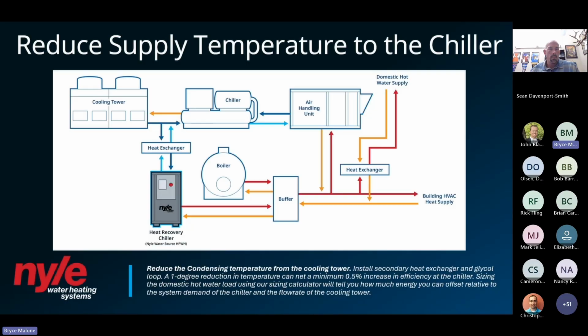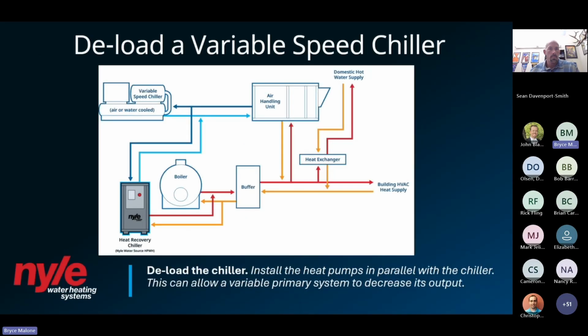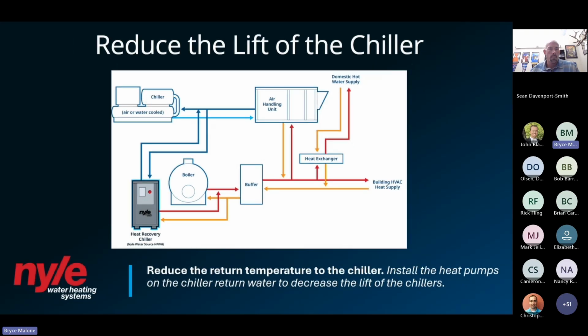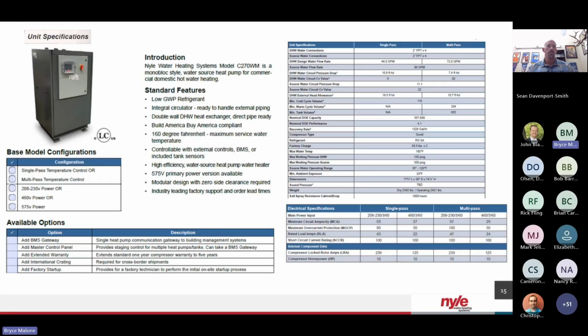That's actually from Johnson Controls. They've studied this at length and actually have great data on how you can impact that. I can deload a variable speed chiller. So if I want to decrease its output, that's another application where I can deploy a water source heat pump water heater, in this case the C270, to also deload that chiller. And I can also decrease the lift, so I can reduce the lift of those chillers as well. So there's more to the deployment of a water source unit in particular, especially as you're talking about other HVAC equipment in the system, that you can benefit from and leverage, not only higher COPs, but also increased system efficiencies in general.